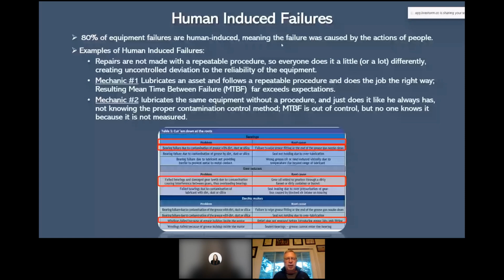I went to a plant one time and they were having a lot of problems with motors. I was there to look at the large horsepower motors they had a problem with. It was kind of interesting because I went out to one, about a 500 horsepower motor, and I looked underneath it and it had a relief plug. I said, you guys removed the relief plug underneath that motor, at the bottom of it? Oh, no. So you lubricate it? Oh yeah, we lubricate it every month. That's why we don't know why we're having those failures. I said, that's a relief plug.